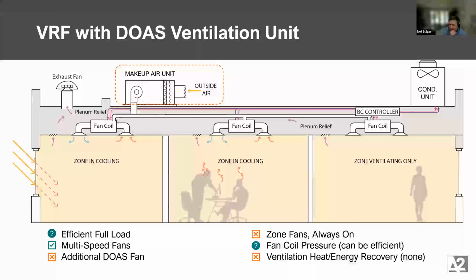I did try and do a run with only the multi-speed fans ducting the outside air to the software, and it did not work for me. There's probably more systems needed, but the outside air, when I only did that, would drop below the minimum ventilation. In this configuration, the outside air was always satisfied. I was always making sure I hit the minimum amount I needed, and my fan coils could go all the way up to their three speeds and then all the way down to a lower speed.